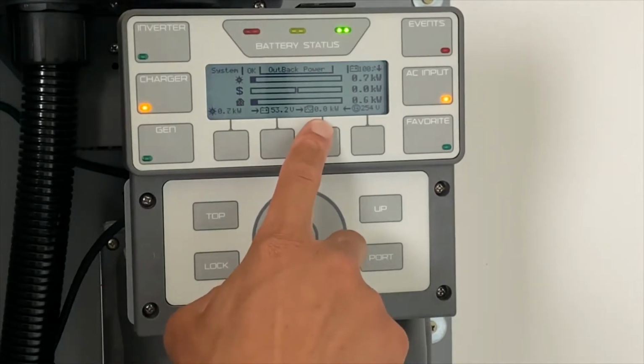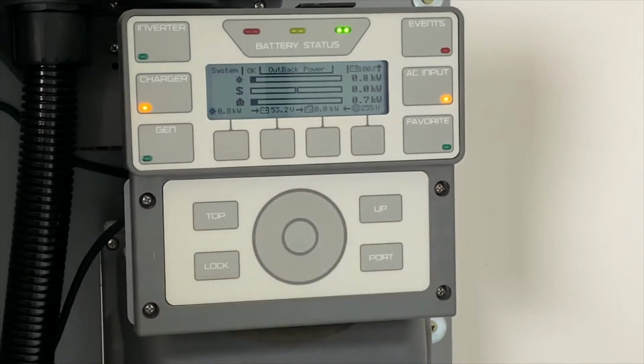The next button we see here is the inverter, and this indicator tells us how much power is flowing through the unit. Right now the system is configured as it would be right after an initial installation. Because there's usually a gap of about 2 to 3 weeks after the system is installed before the power company installs your new meter, the system's not operating at full power now - I'll show you a little later in this video how to activate the grid sellback feature. Right now, this is just operating as a backup system.